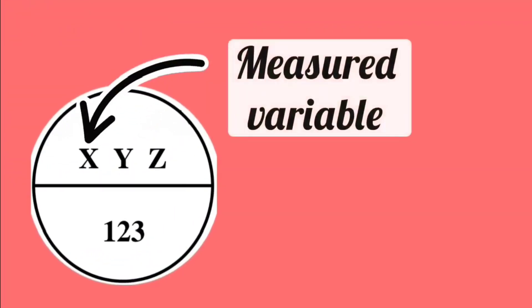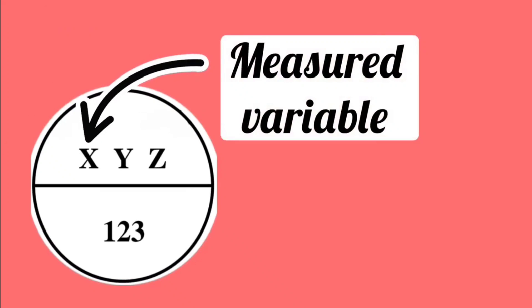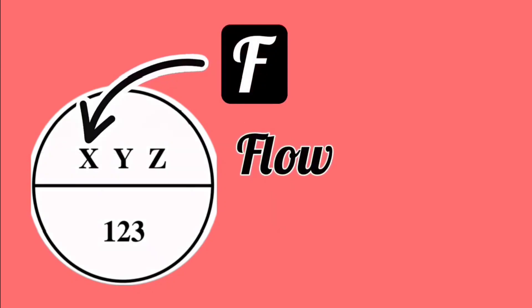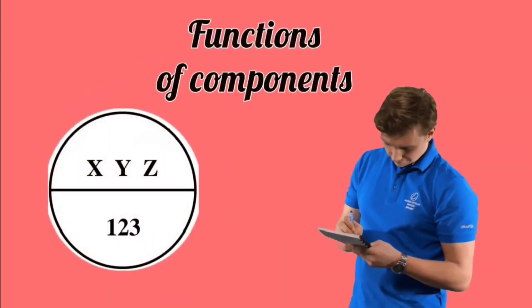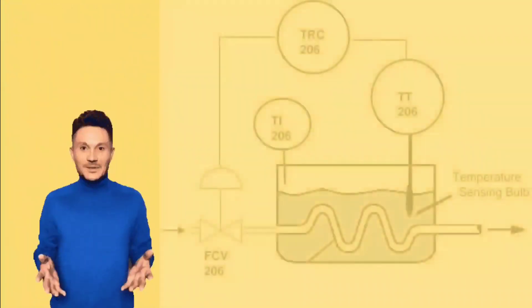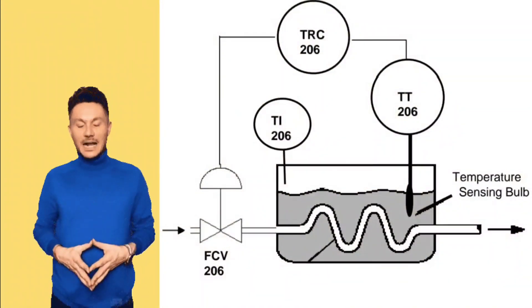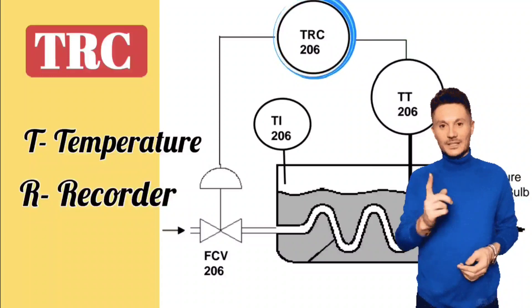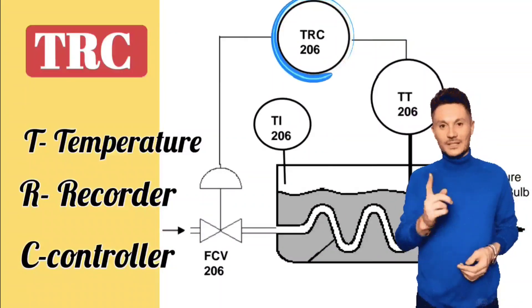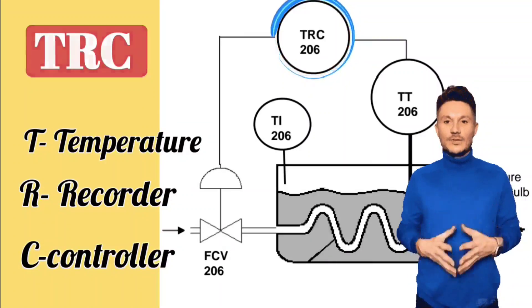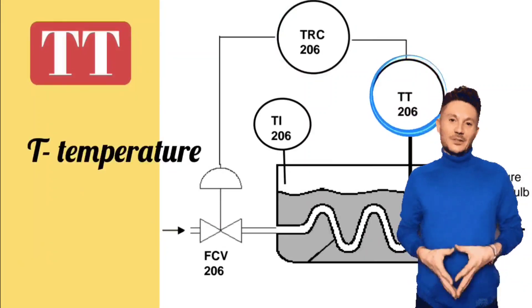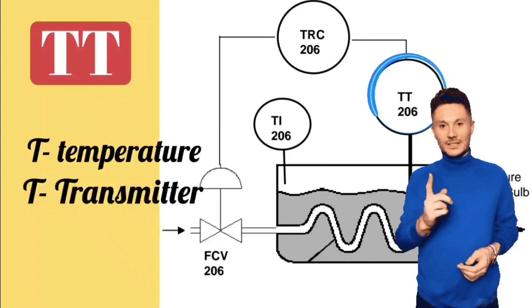On the first letter, if P is written, it means pressure. T stands for temperature, L stands for level, and F stands for flow. The rest of the letters tell the functions of the components. Let's take a small example. Here, TRC stands for T means temperature, R means recorder, and C means controller, which records or measures the temperature and also controls. If TT is written, first letter stands for temperature and second letter stands for transmitter.